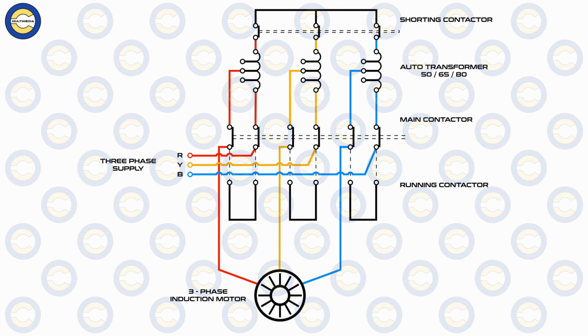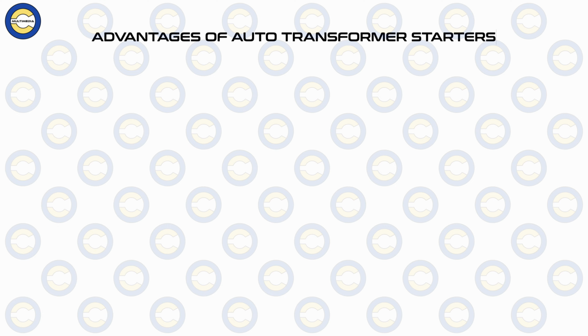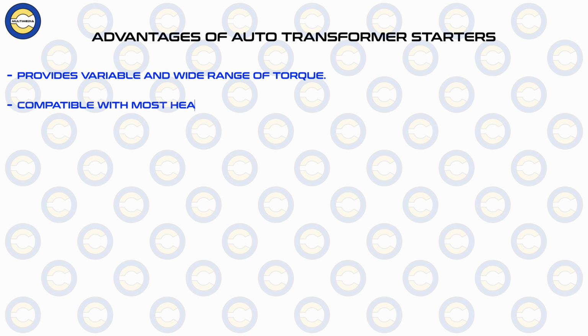So once going through all these details of the auto transformer, now we are in a good position to understand their advantages over the other starting methods. As we just discussed, it will provide a very variable and also a very high peaking range of starting torque per ampere of the line current being drawn. This is by virtue of the flexibility of the voltage tapping that can be variably adjusted depending upon the load requirements.